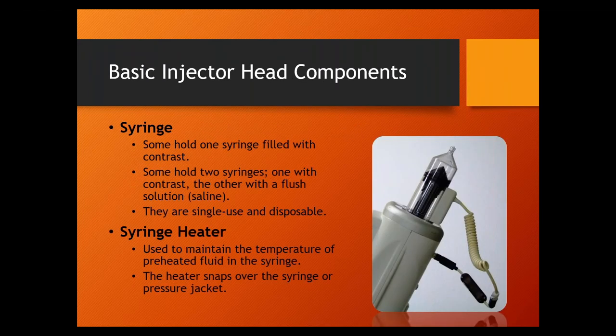Syringes, like I said, are one-time use only. Another thing about syringes: with just a couple exceptions, they are model-specific. These are Stellant syringes and they only fit on this model - you cannot put them on other models. The exceptions are typically when a new model comes out and replaces an older model and they don't redesign the syringe. For example, the Mark V Plus and the Provis - the Provis is newer but uses the same syringes as the Mark V Plus. But for the most part, syringes are model-specific.